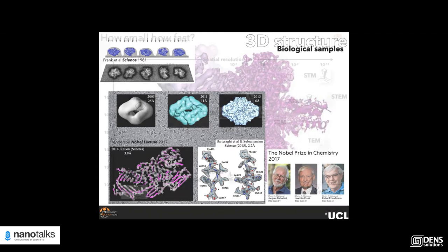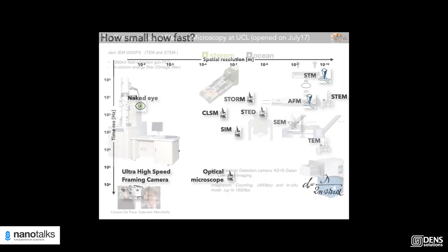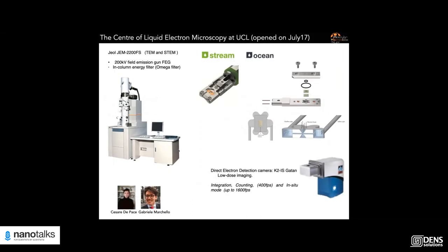Nowadays it's not only about how small can you image, but how fast. With the development of new detectors we can now acquire fast frame videos, which are needed for capturing dynamic processes. The Center of Liquid Electron Microscopy at UCL comprises a JEOL JEM 2200FS, a 200 kV FEG microscope with an in-column omega filter. We have two liquid holders from DENS — the new generation stream holder and the first generation ocean holder. The work I'm going to present today was done with the ocean holder and a direct electron detection camera, the K2 in situ from Gatan, which allows low-dose imaging.